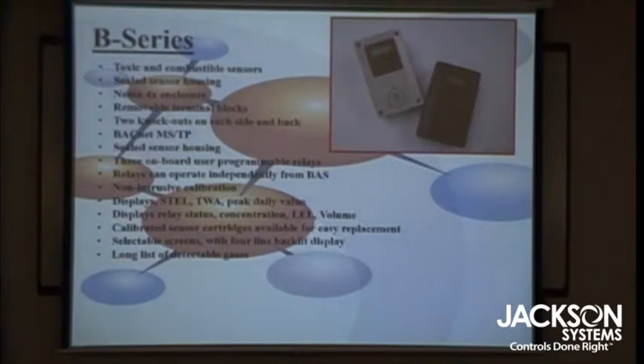We have another version of it, which is a BACnet version, and is a full BACnet MSTP. When we designed it, the prototypes we sent to Reliable Controls and to Delta and to Johnson's and Siemens. They tested it out and told us what we had to change, and we did it. And the result is a fully compliant BACnet gas detector that will work on any system. And it's one of the truly ones that are fully BACnet.